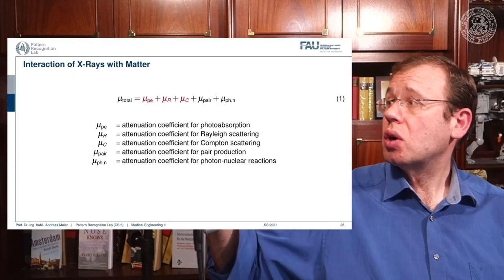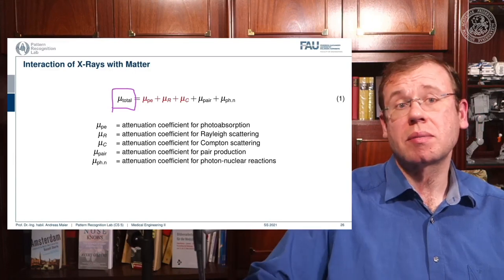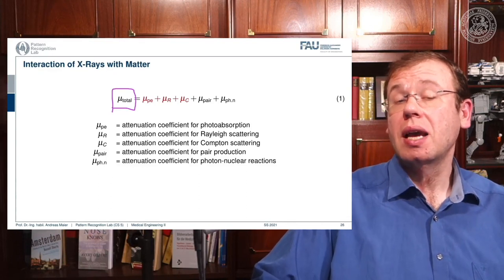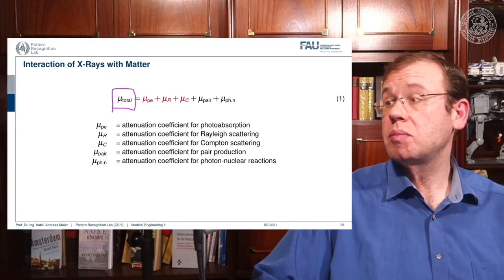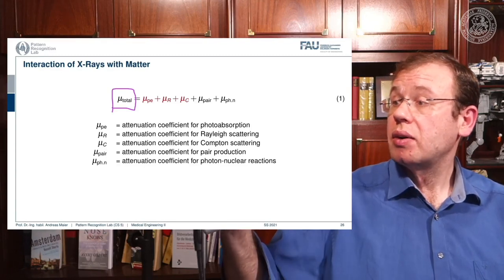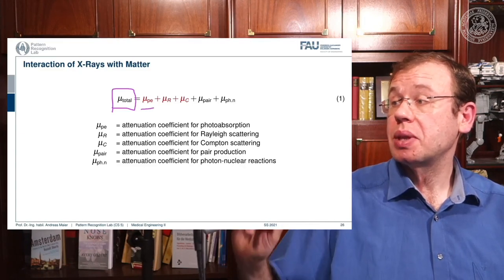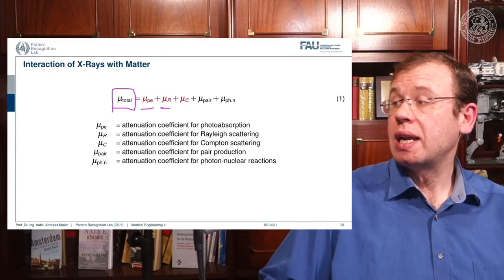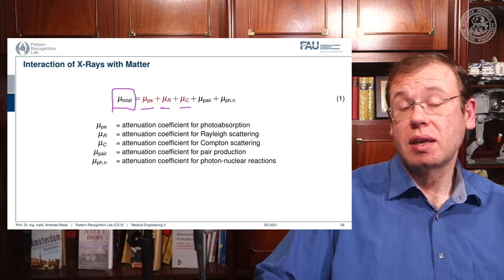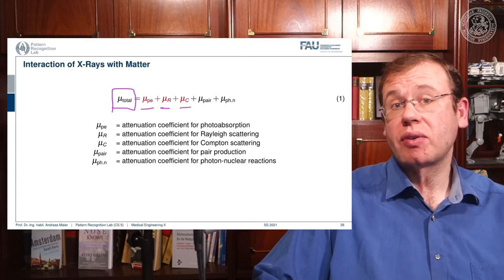One thing we should talk about is how mu is actually composed. Mu is a material-dependent characteristic, but it's composed of a series of different effects. There is mu-PE, which is photoelectric absorption; there is mu-R, which is Rayleigh scattering; and there is mu-C, which is Compton scattering. These three effects are relevant for most x-ray imaging.